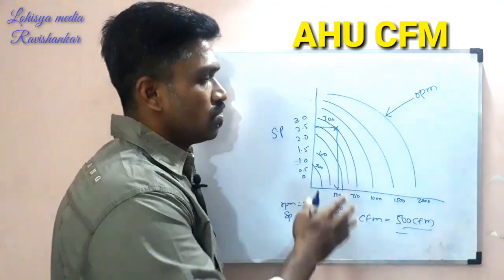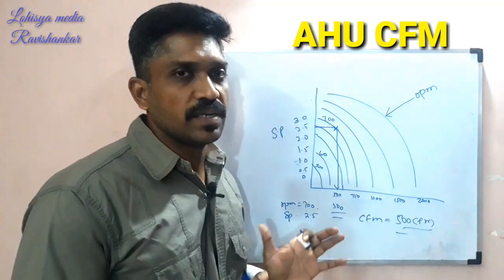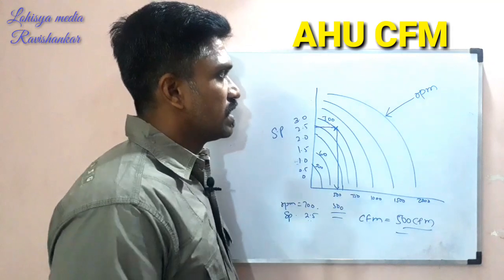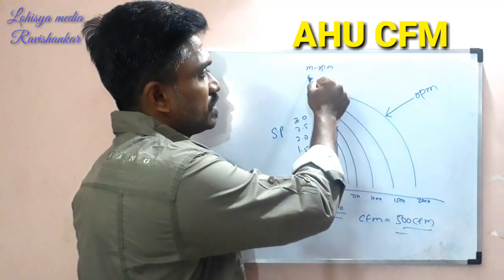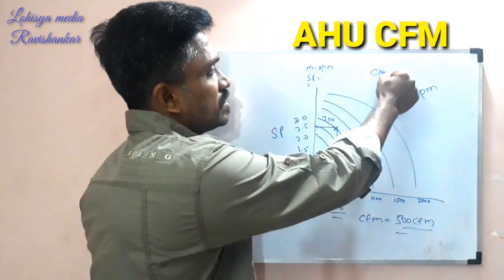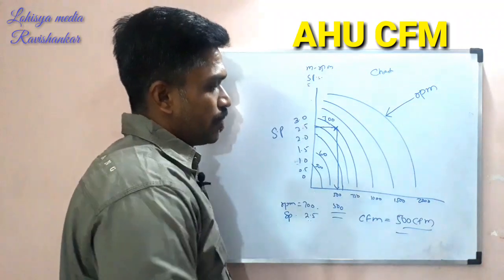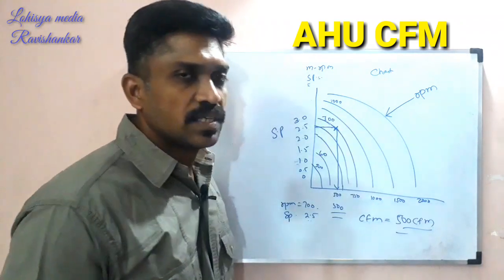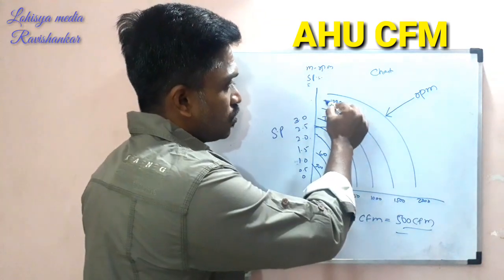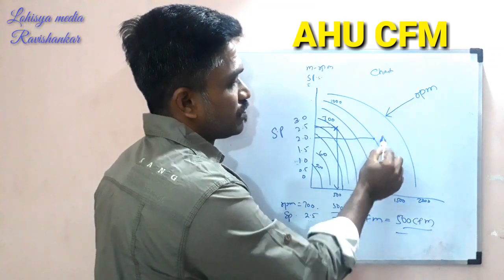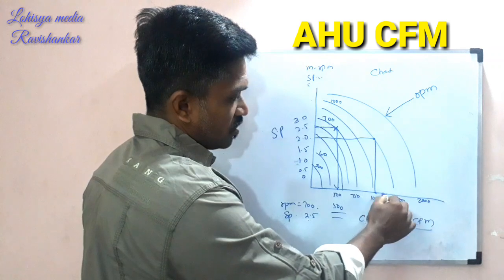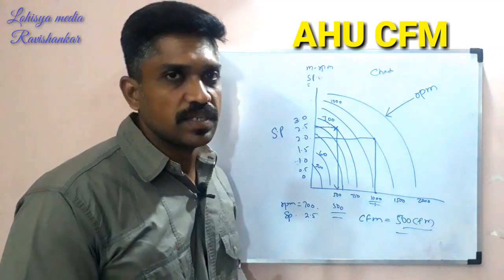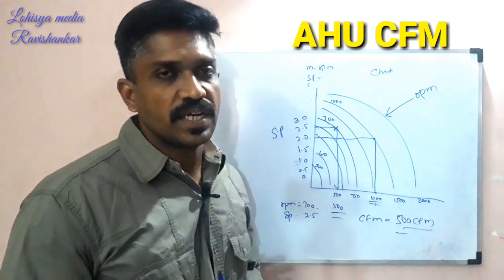You can use this method. This is a simple and basic method. We need motor RPM, static pressure, and a chart — these three inputs. For example, suppose the motor is 700 RPM and static pressure is 2.5. In the 700 RPM line, the AHU is 580 CFM. Now you can calculate the CFM — AHU is 580 CFM.